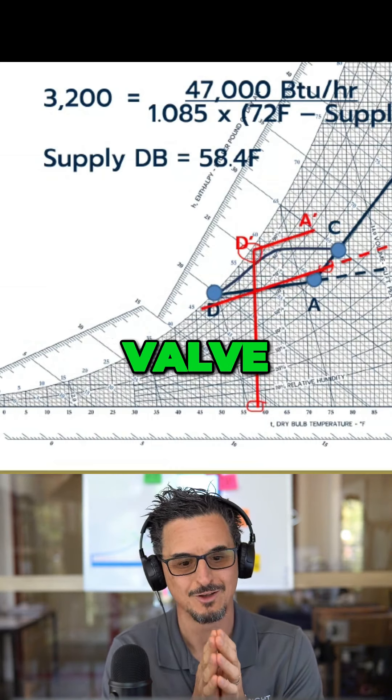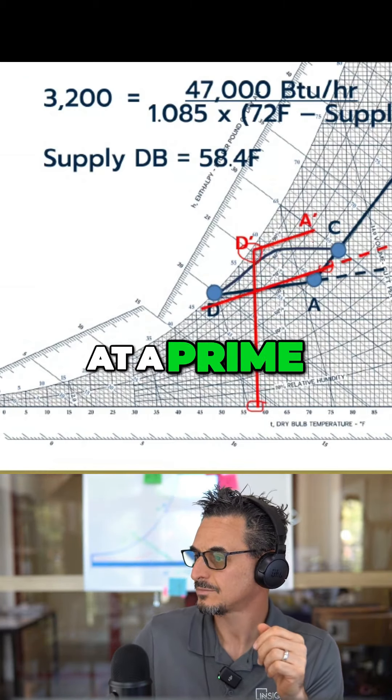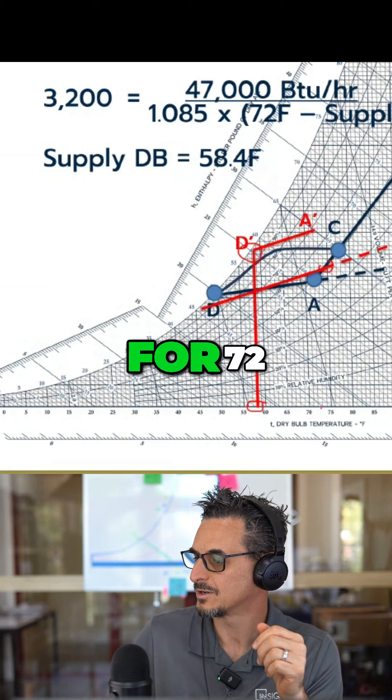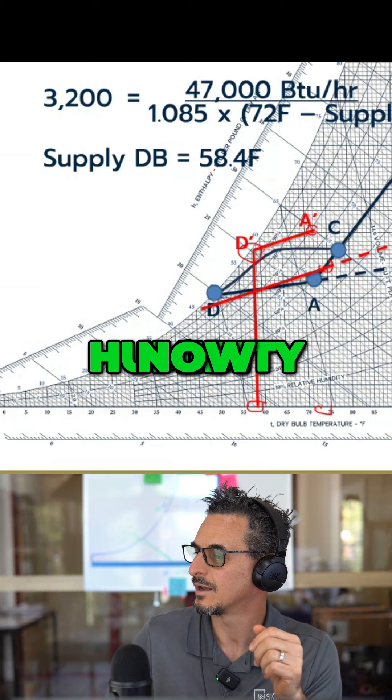Constant volume systems, modulating chilled water valve, not really fully understanding what happens at part load. So you see it, what's the problem at A prime? Well, we're okay with our space temperature, we're 72 degrees, but look at our relative humidity. Now it says 70% RH, which is at about 60 dew point.